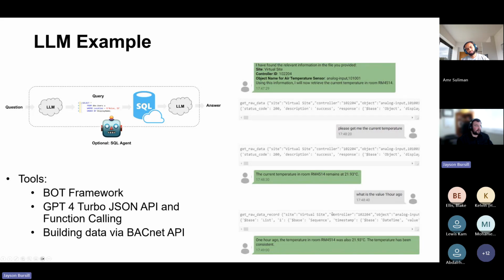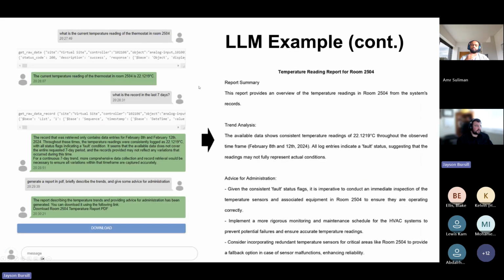This starts to get particularly interesting when you ask for the record over the last 7 days, and it starts to think something's wrong here. I didn't mention this before I introduced the problem, but we were running this with a virtualized controller, so it didn't have real inputs connected—it had a static reading the whole time. From this, it was able to notice the reading was static over the last 7 days and say that it was in a fault condition.